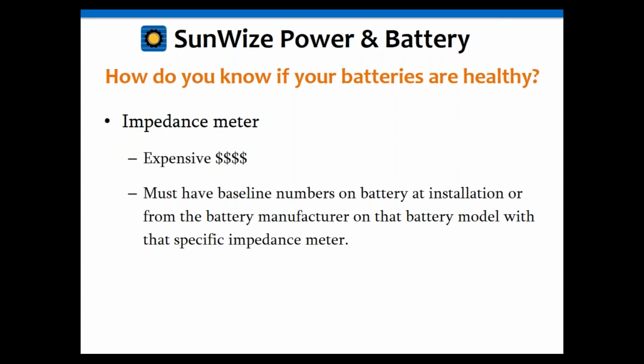And the key there is you have to have a baseline number. These things measure an impedance in the battery. They're great because you can get a number really fast, and they can be done with the batteries online. So you don't have to take anything offline. You don't have to turn off the charge. You don't have to disconnect the load. You don't have to do anything to them. You can just put this meter on them like you would a voltmeter and measure the battery terminals, and it spits out a number. The thing is that it's worthless without a baseline number.